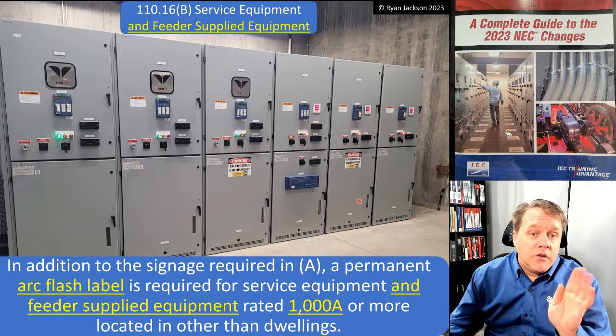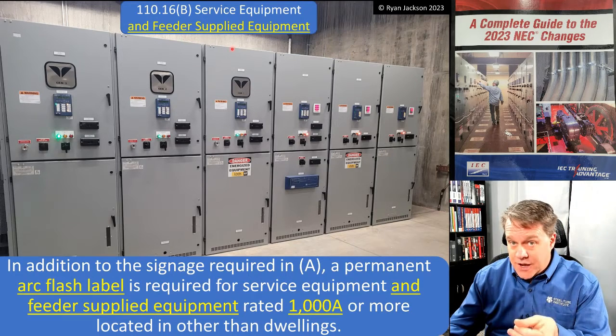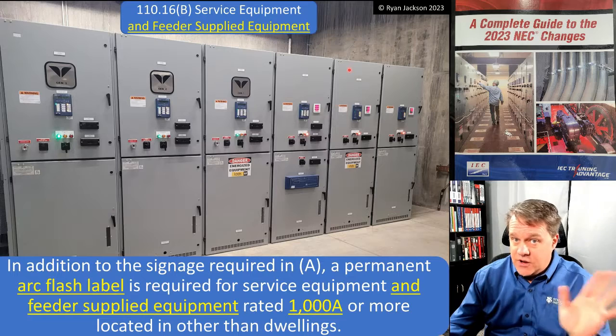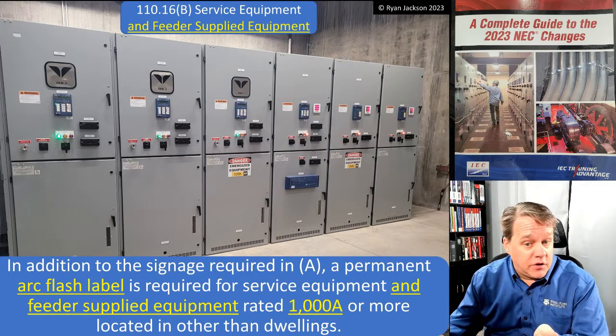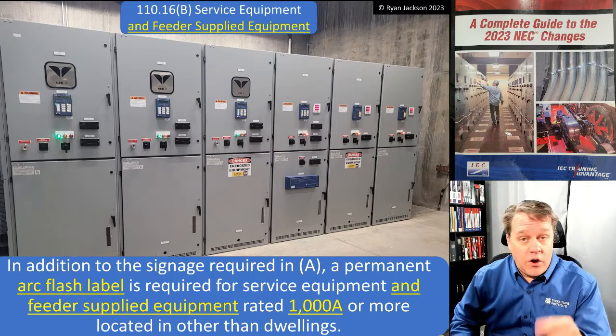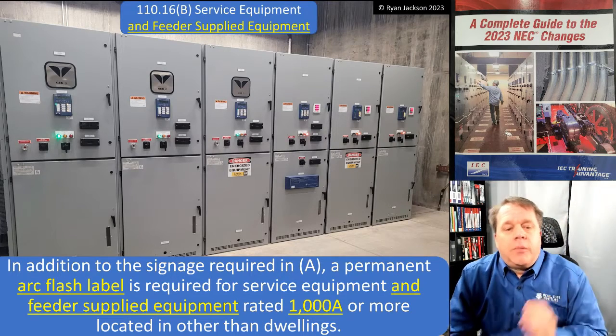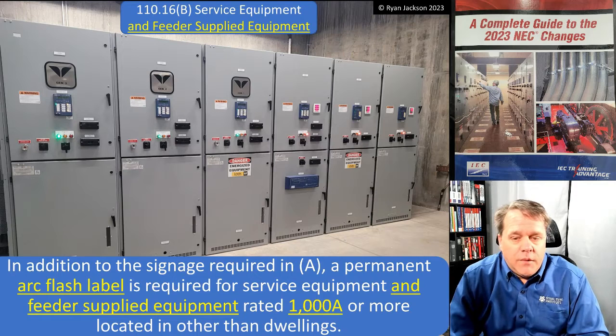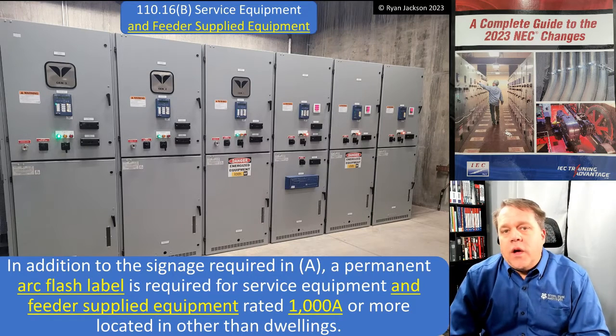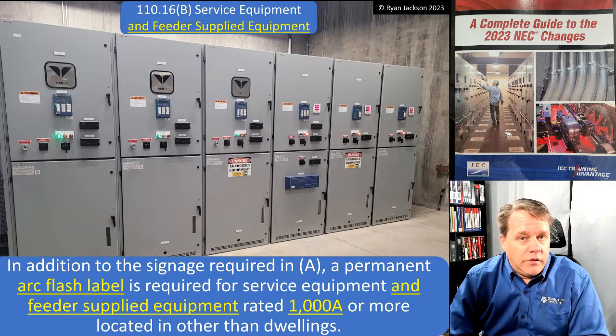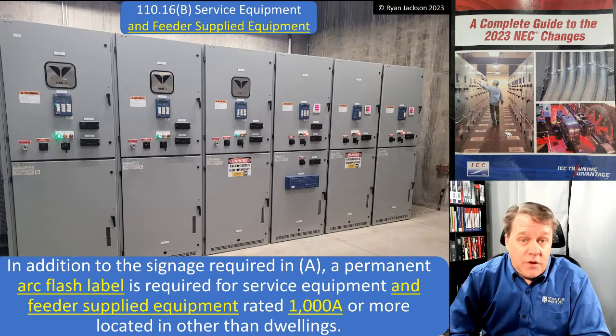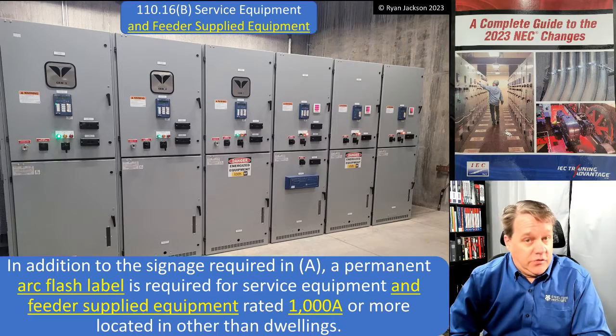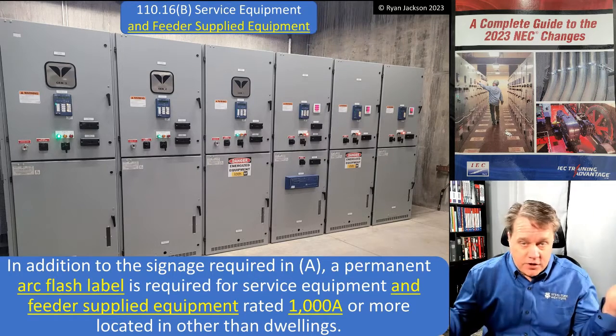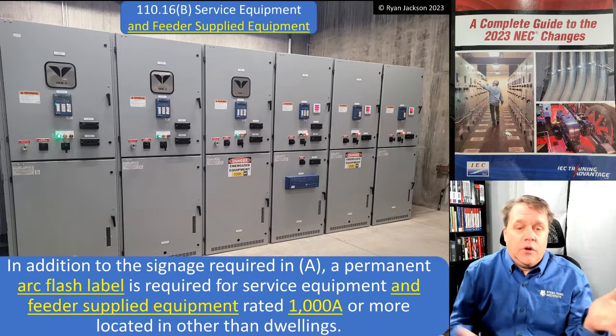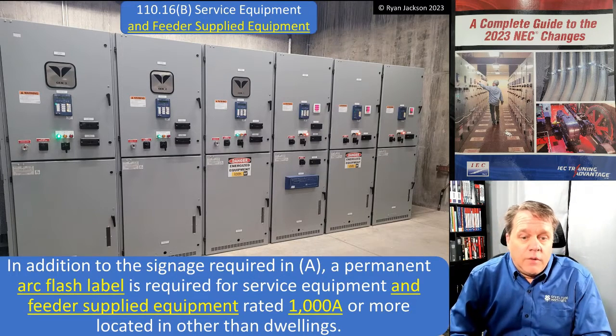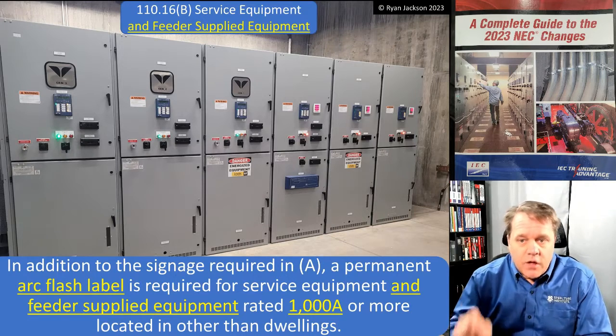This, first of all, service equipment or feeder supplied equipment. All right, so it doesn't matter, not just the service disconnect, anything that's supplied by a feeder circuit as well. In addition to the signage required in A, warning arc flash, a permanent arc flash label is required for service equipment and feeder supplied equipment, rated 1,000 amps or more, located in other than dwelling units. All right, so certainly this piece of equipment is either supplied by a service or by a feeder, right? Just by definition, it couldn't possibly be supplied by a branch circuit. So this thing is rated 1,000 amps or more. It must have some other signage.